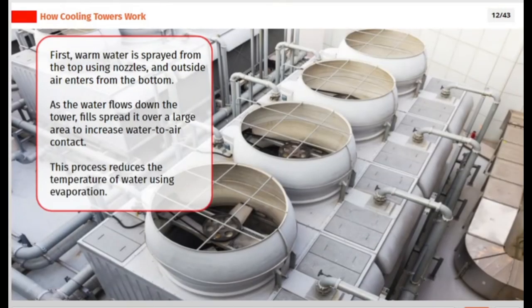First, warm water is sprayed from the top using nozzles, and outside air enters from the bottom. As the water flows down the tower, fills spread it over a large area to increase water to air contact. This process reduces the temperature of water using evaporation.